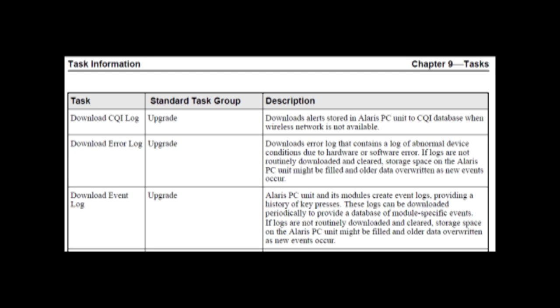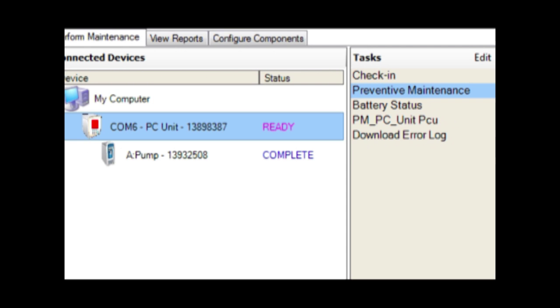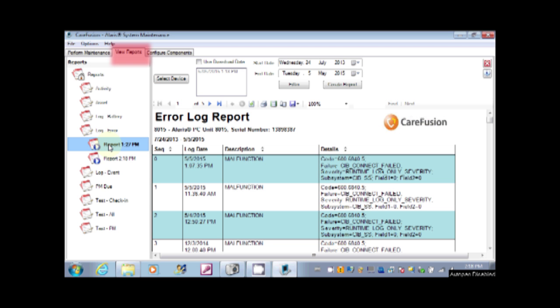We will now look at downloading the error log and viewing the report. This is quite handy. This is just a section from the manual. So we are downloading an error log, but equally you could have downloaded an event log, CQI, battery log, or many others. I have added a task list there to download the error log. What we would do is run that task, and then once that is run...